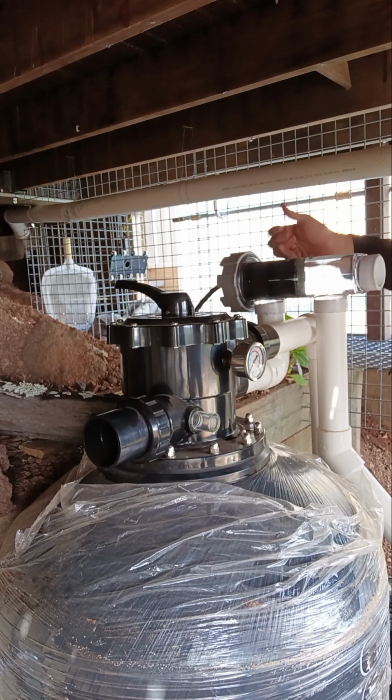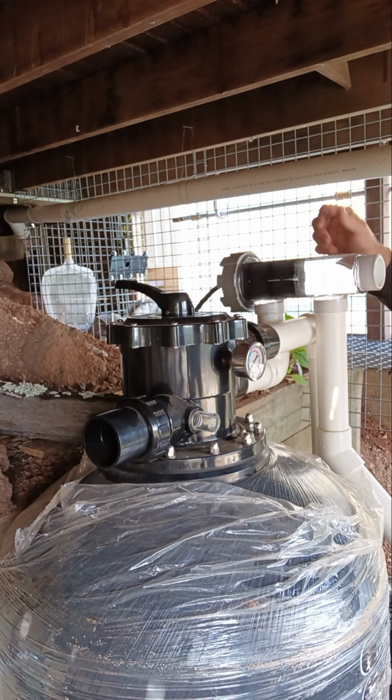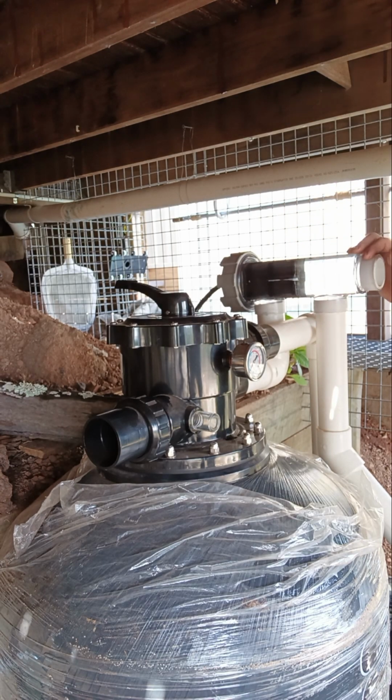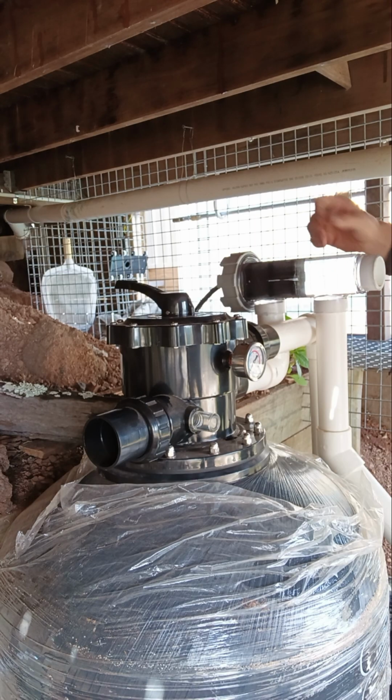Calcium is the byproduct of chlorine production, so over time it'll start to build up. If it goes white there, we reduce the cell cleaning to 6 hours, which is more often. That's correct, exactly right. So you will see little bits building up, and that is normal. It's if it's completely caked that it's a problem.